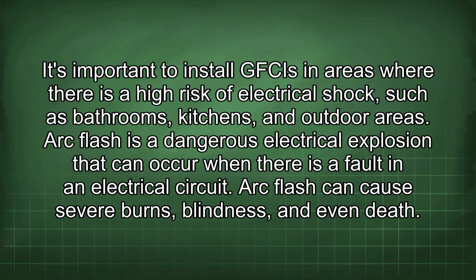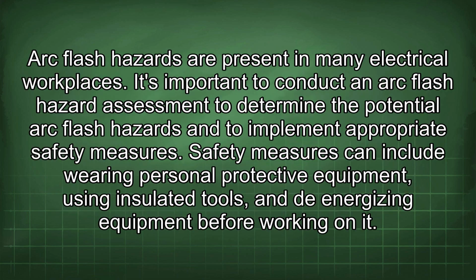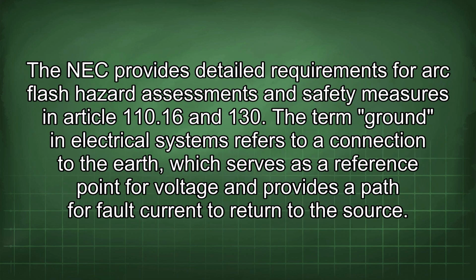Arc flash is a dangerous electrical explosion that can occur when there is a fault in an electrical circuit. Arc flash can cause severe burns, blindness, and even death. Arc flash hazards are present in many electrical workplaces. It's important to conduct an arc flash hazard assessment to determine the potential arc flash hazards and to implement appropriate safety measures. Safety measures can include wearing personal protective equipment, using insulated tools, and de-energizing equipment before working on it. The NEC provides detailed requirements for arc flash hazard assessments and safety measures in Article 110.16 and 130.